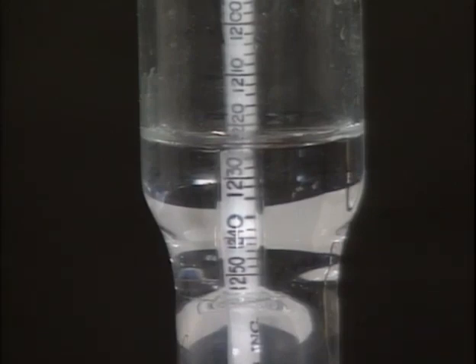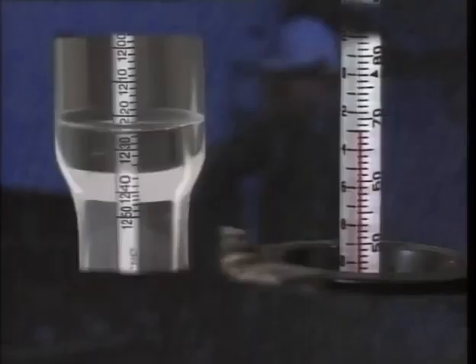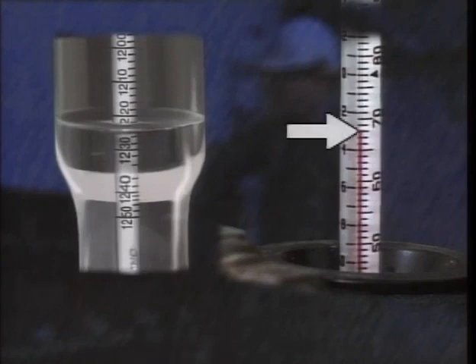Specific gravity is affected by temperature, so the reading may need to be corrected for the temperature of the electrolyte. Electrolyte temperature may be checked using a cell thermometer. Here the cell temperature is 68 degrees Fahrenheit.